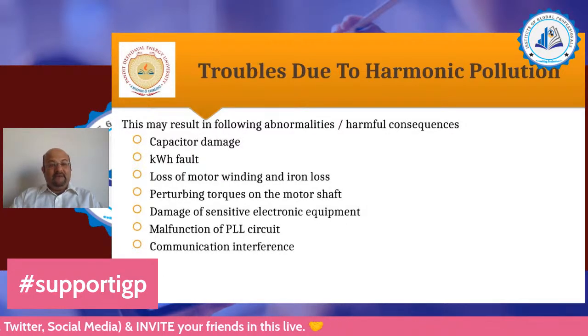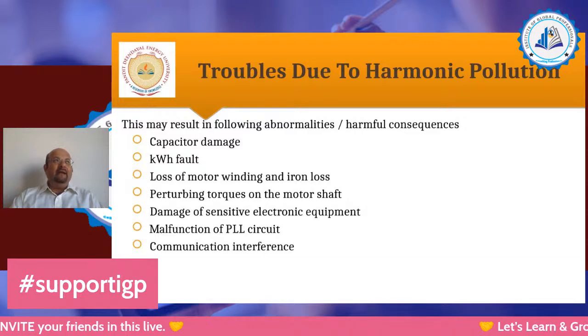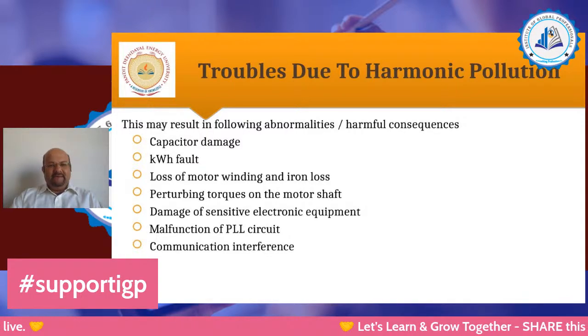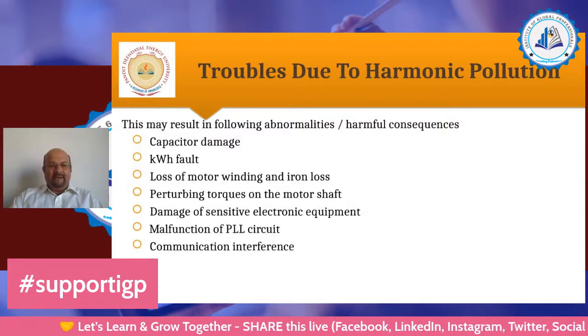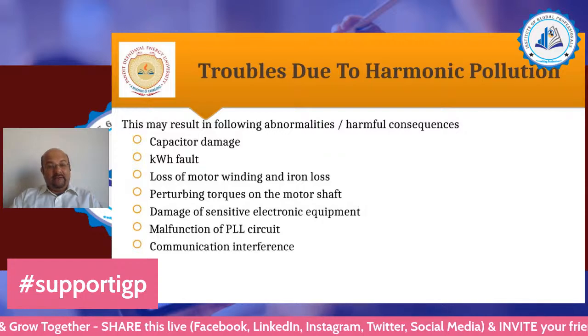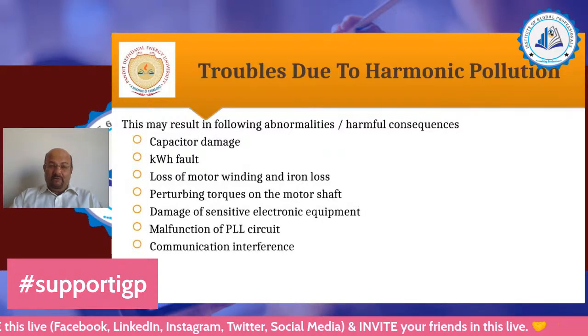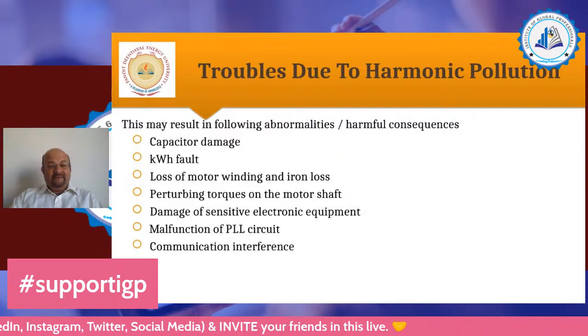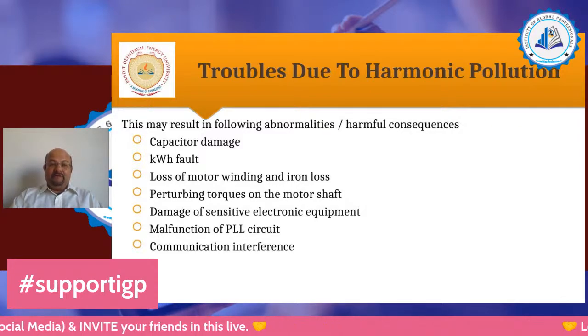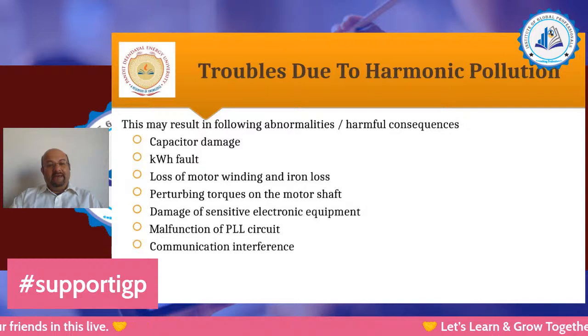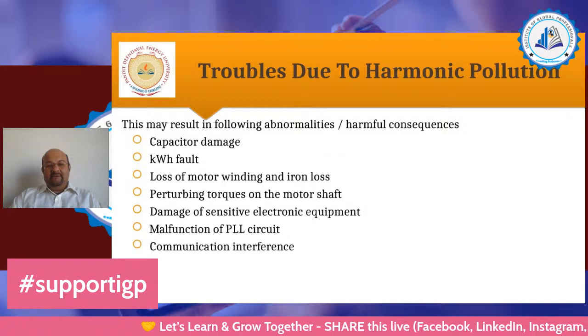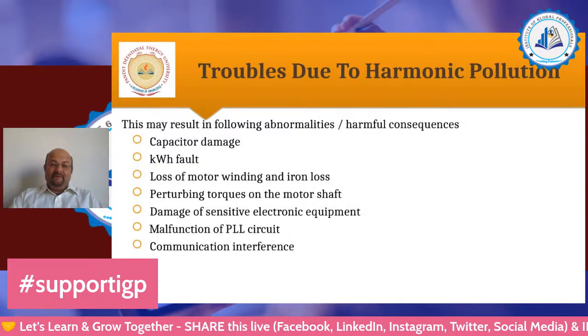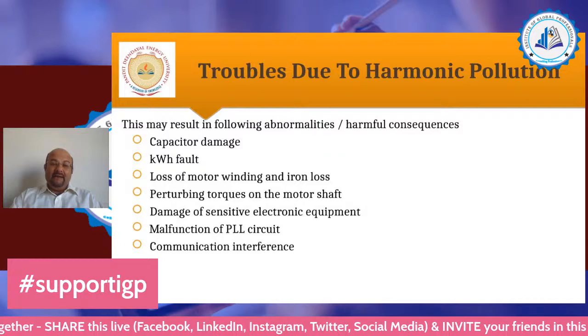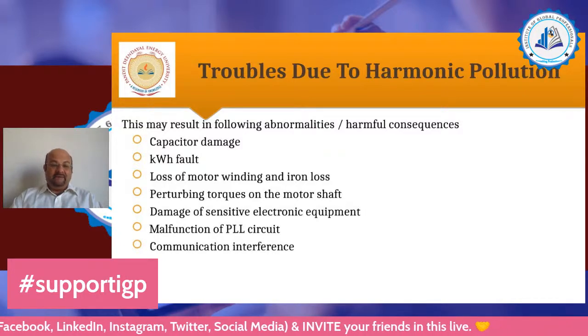Then comes capacitor damage. Here also I'd like to explain how a capacitor fails. We know that a capacitor is a device having two conducting plates separated by a dielectric. And what is a dielectric? Dielectric is an insulation material. And as we already know now, insulating material is very sensitive towards temperature. So any temperature beyond the designed one will drastically reduce the life expectancy of the insulating material, and hence the capacitor may get damaged or may fail before its life ends.